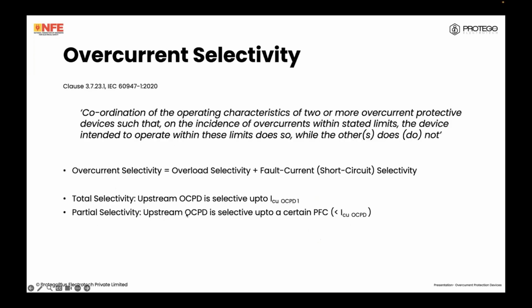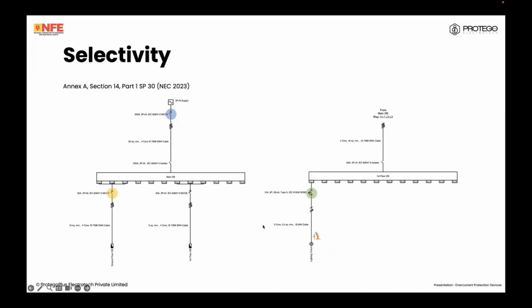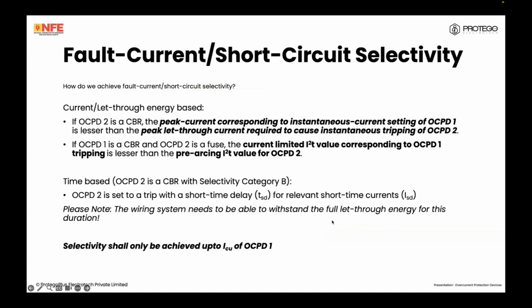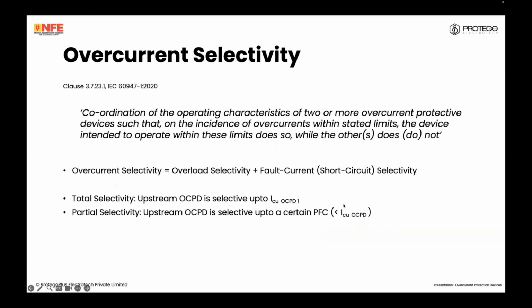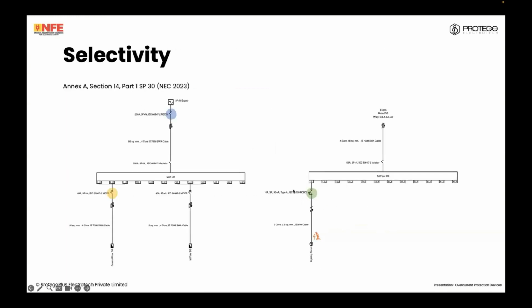Partial selectivity means the upstream OCPD 2 is selective up to a certain prospective fault current. So say if there's a fault here and this circuit breaker is immediately upstream of this, and this circuit breaker is upstream of that one, I am saying that for faults up to 4.5 kiloamperes, only this OCPD will trip. For faults greater than 4.5 kiloamperes, this OCPD will trip. That is called partial selectivity. And obviously, these can only be defined up to the ultimate breaking capacity of this device. If you have a fault greater than the ultimate breaking capacity of this device, it obviously has to trip. Otherwise, there'll be damage to the protective device. There'll be arcing. You'll have a lot of damage. That's a whole mess. Just remember that.